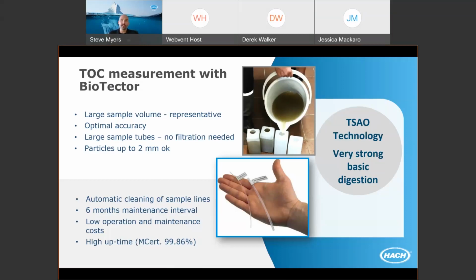This helps us make sure that sample is representative, first of all, to maintain accuracy, but also allows us to use relatively large tubing in the device so we can bring up to 2 millimeter soft particles in there and fully oxidize them and get some accurate results. Also, it's set up to do automatic cleanings with acids between every measurement cycle. And all this combines together to have a pretty long maintenance interval.